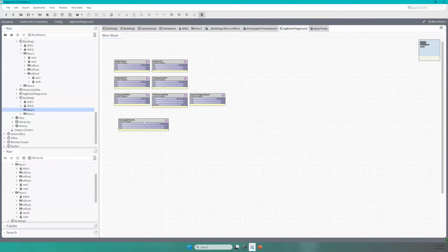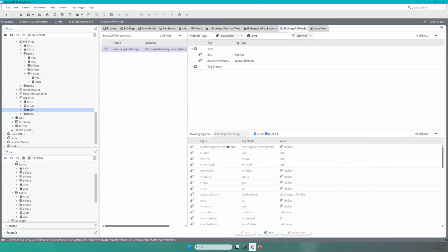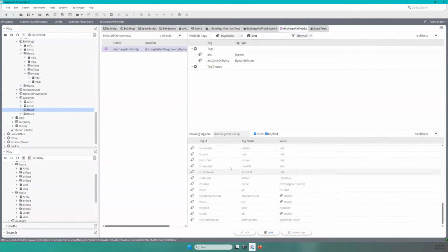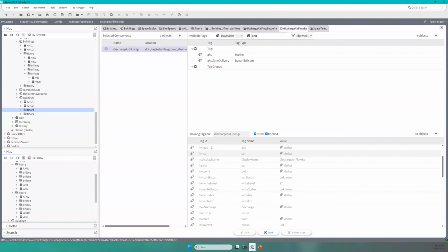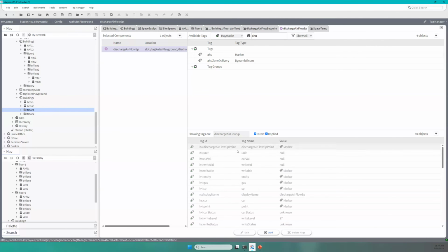When you look at this, I've got that tag rule running. So I almost did the old way. That's like muscle memory. If we go over here and look at the tag manager on that, I applied essentially no direct tags to this. So that means the rule ran and applied the airflow set point, and it applied other things like it's a set point, it's a gas. So here, just based on the name, I've done nothing other than name that point, and then everything is applied appropriately. If you want to call that auto tagging, you can call it auto tagging.